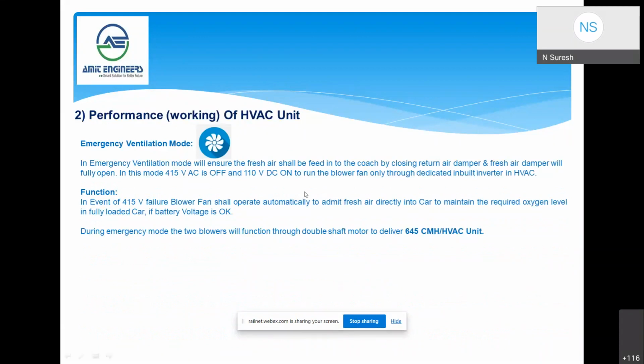This is the emergency ventilation mode. In case of failure of 415 volt, there is an emergency inverter inside the system. In this case, the return air damper will close and only fresh air will be supplied, so that passengers will not feel any suffocation inside the coach. And the airflow defined in the specification is 645 cmh per HVAC unit. That much it will deliver.